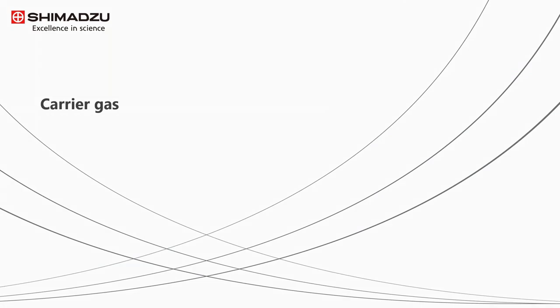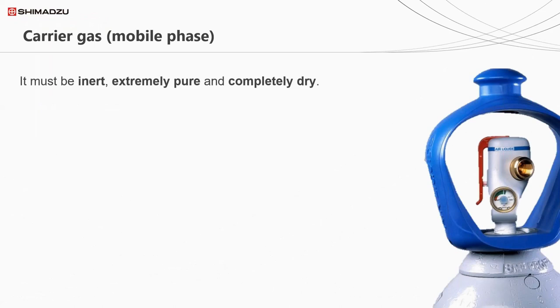Speaking of carrier gases, one of the most important decisions you'll make when operating your GC and developing new methods is how to use your carrier gas and which choice of gas. As a general rule, there are some things we require from a carrier gas: it must be inert, extremely pure, and completely dry. Your gas should not react with your sample in any way, should be pure and free from contaminants, and certainly free from moisture. The reason is that any contaminants within the carrier gas will be detected by the detector and could have an adverse effect on your chromatography and lower the sensitivity of the system.